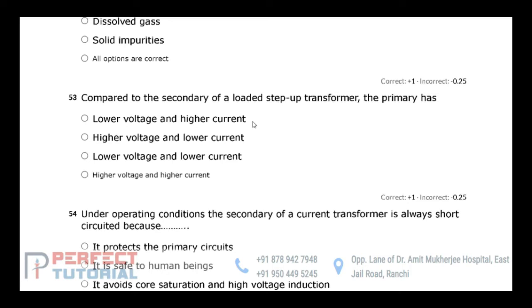So सवाल पूछ रहा है एक स्टेप अप ट्रांसफार्मर के सेकेंडरी के कंपैरिजन में प्राइमरी का क्या होगा? स्टेप अप ट्रांसफार्मर मींस primary side would be your LV side and secondary side would be your HV side, and LV side voltage reading is lower than HV side voltage reading, and current reading is higher than that in case of HV side current reading. So compared to secondary of a loaded step up transformer, the primary has what? Lower voltage and higher current.